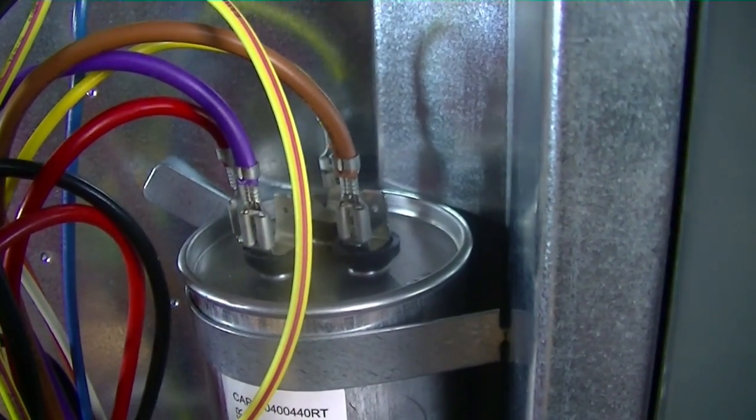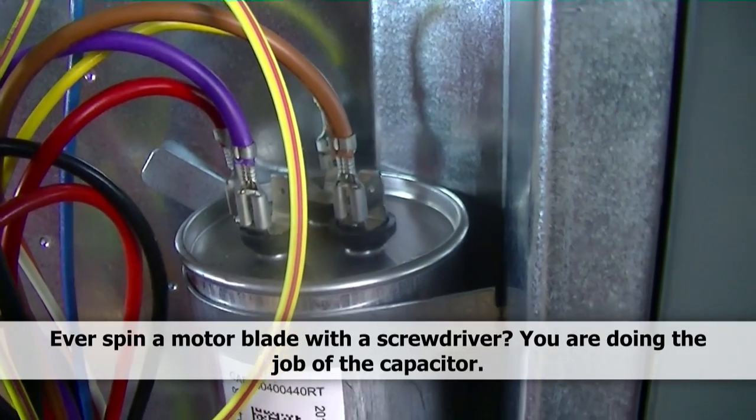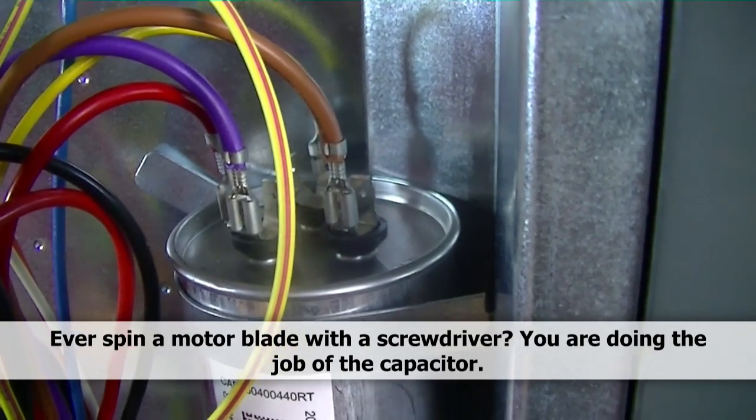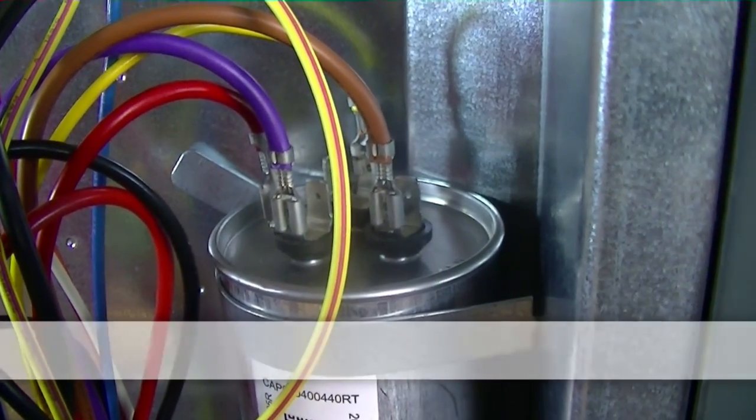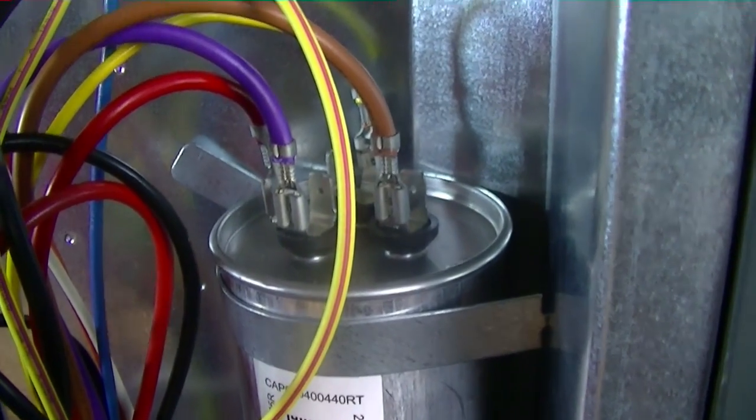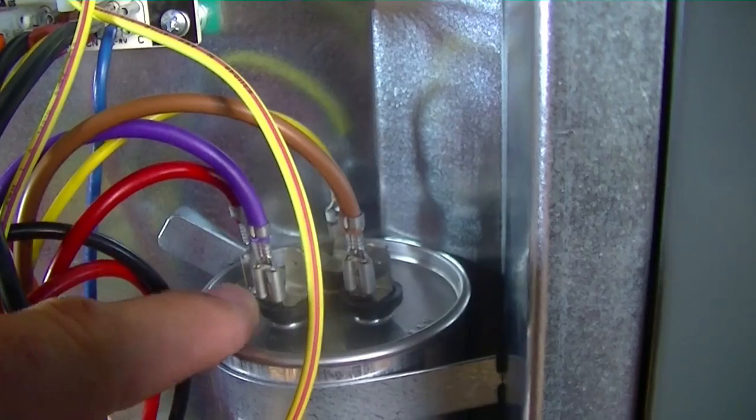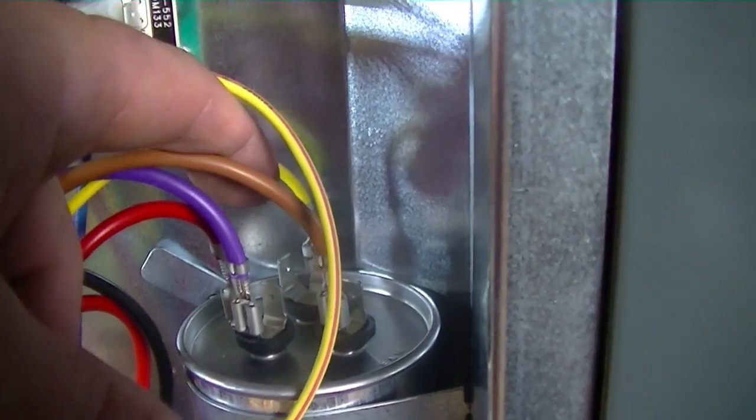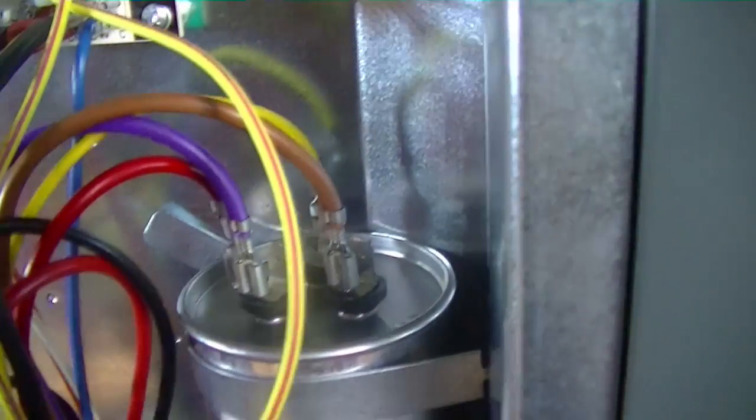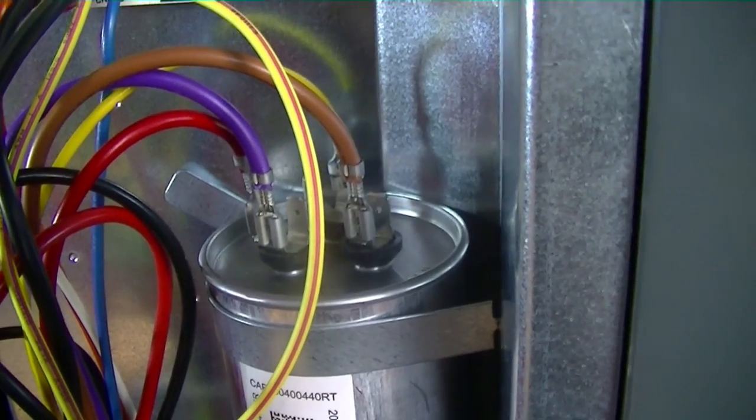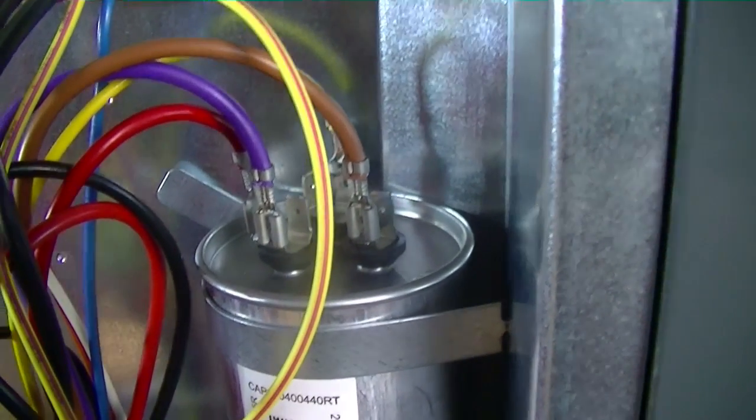If the capacitor is weak, the fan motor may turn at a lower RPM or not start at all. If the compressor side is weak, since we're talking about dual run with a shared common terminal and a dual run capacitor, sort of a run capacitor for the compressor and a run capacitor for the fan motor. If the compressor side is weak, generally the compressor does not start at all.